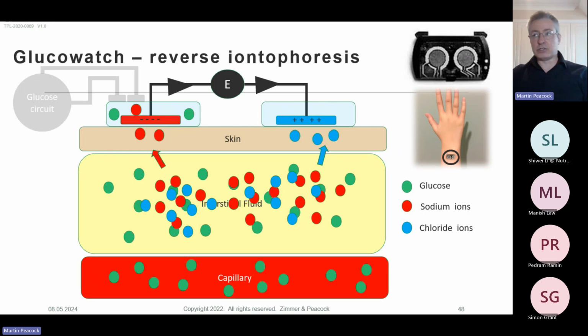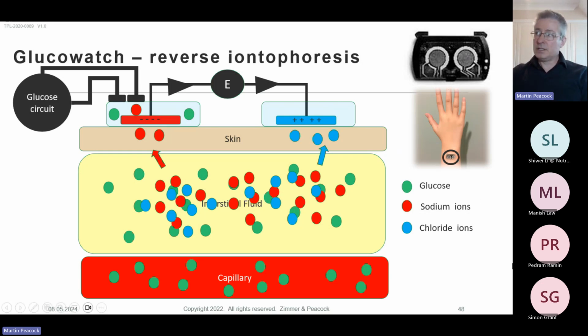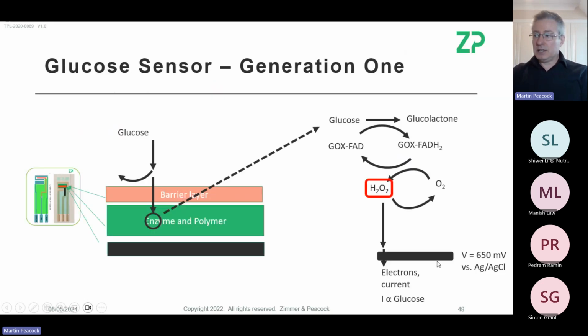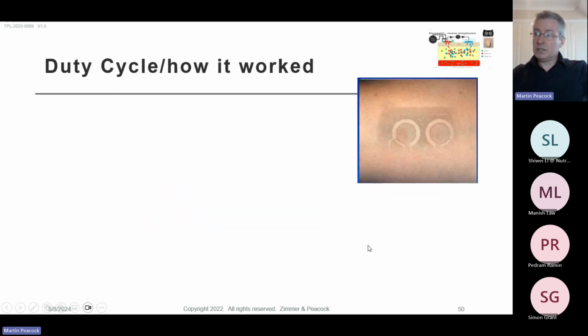And these ions are meant to then drag the glucose with it. If you've got a background in electrochemistry, you can look at the electrode layout and see that there's at least two circuits involved here, and it says it here as well, one for applying the voltage and passing current, and one for then measuring the glucose signal. I think they were using a generation 1 glucose sensor. At ZP, we have generation 2 glucose sensors. We also have non-oxygen versions of glucose sensors as well.